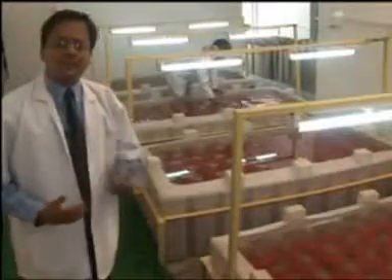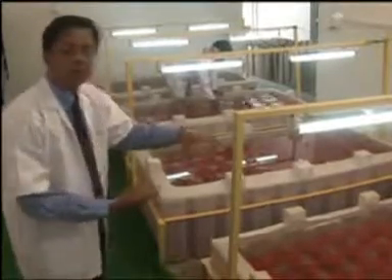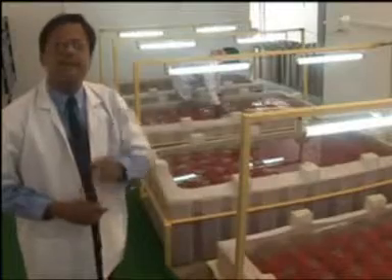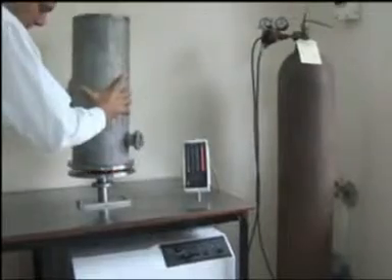The first of three quality tests is a 24-hour leak test where each extinguisher is left submerged in water for 24 hours — an upturned beaker tracks any bubbles that might escape, signaling a leak. The second is the helium detection test to detect nitrogen leakage. This involves detecting minuscule quantities of helium leakage in a vacuumized chamber. Helium is a trace gas injected into the extinguisher along with nitrogen in order to test for leakage more thoroughly. Every single ceasefire extinguisher is helium tested, and each piece that passes the test bears a certification to that effect.